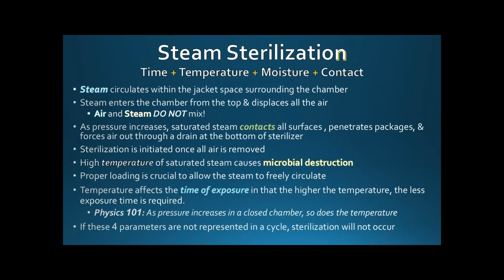So there are minimum standards. Again, IFU is so important. Depending on what type of sterilizer you're using and what type of sets you're using, you have to follow the appropriate exposure time. Like I said, a lot of times we use the pre-vac because it's a shorter exposure time, and it's only a 4-minute exposure time. But again, the IFU for your instrument could be 8 minutes, could be another time. So you have to know the IFU for all your instruments, and then use the exposure time based on whatever's the longest in that load. That's why it's so important to know your IFUs.